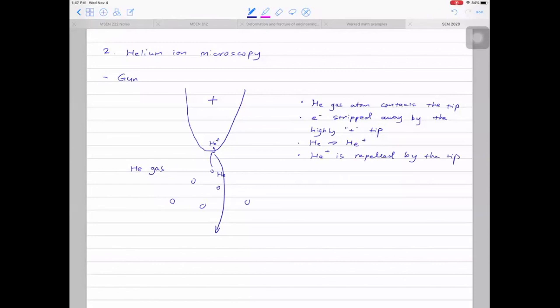In SEM, electrons from the source are emitted and interact with your specimen. But in helium ion microscopy, the electrons are stripped away and the helium ions hit the specimen surface. It's similar to a gallium source, but not exactly the same. In a gallium source you have liquid metal, whereas here you have gaseous helium turned into ions, which then interact with your specimen.